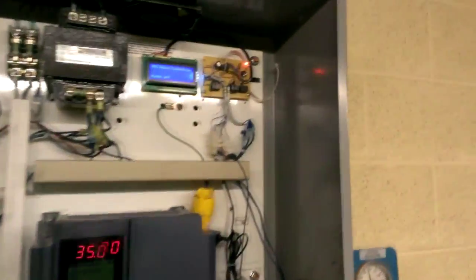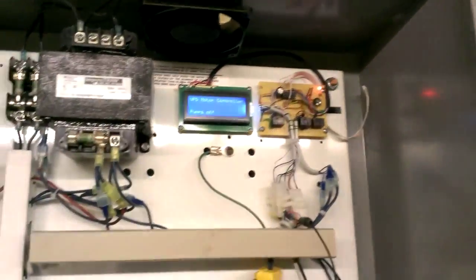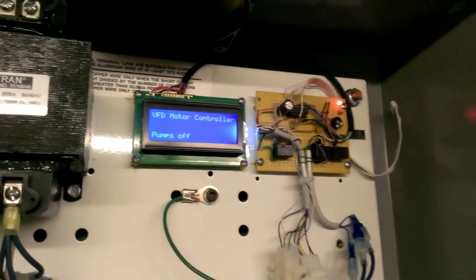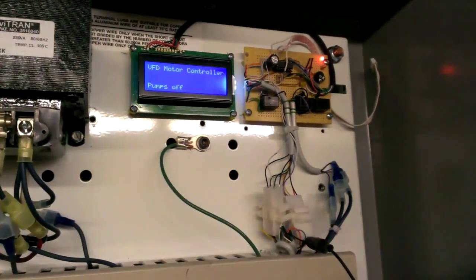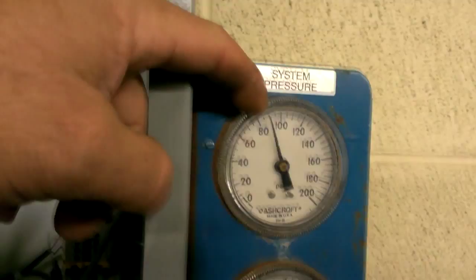So far I left it running on manual. My controller's not running the VFD yet, so it just shows it off. Looks pretty cool though. I just got it on manual, set for 35 hertz. The pressure's still a little high, but it's better than it was — closer to 120 earlier.